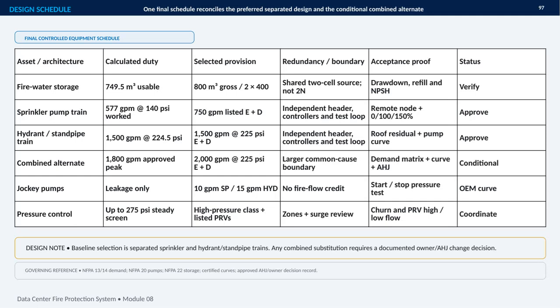This slide presents the final controlled equipment schedule, bringing the preferred separated design together with the conditional combined alternate. The baseline is clear. Sprinkler and hydrant or standpipe systems remain separate, with independent headers, controllers, and test loops. That separation is the governing design selection. For firewater storage, the schedule provides 800 cubic meters gross, arranged as two 400 cubic meter cells, while recognizing that this is a shared source rather than a fully 2N arrangement.